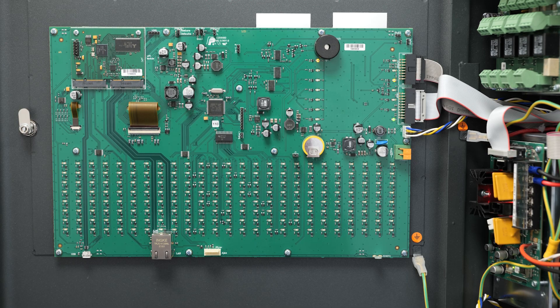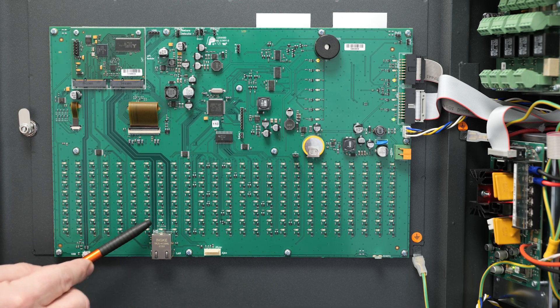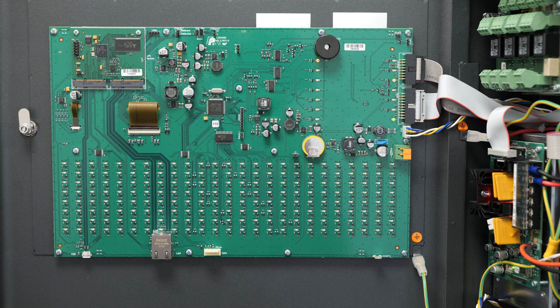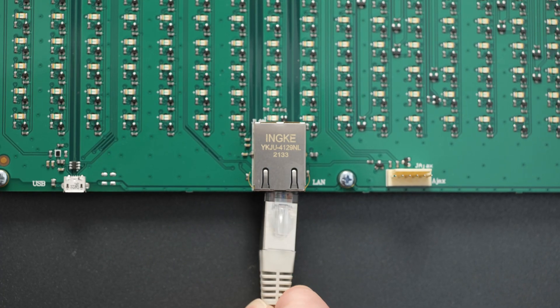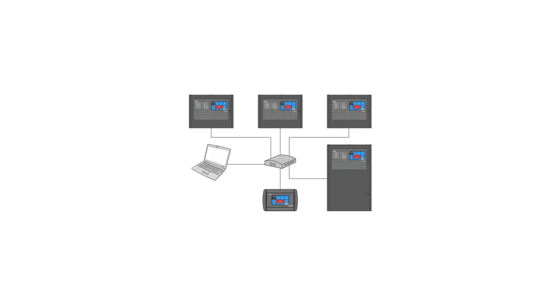As mentioned earlier, we can use the built-in LAN module of the Iris panels to create a network. We can use a standard CAT cable to connect the Iris panel to the LAN network. We have two options: to connect the panels over the internet, where every panel is online using a real IP and we are not limited in distance between the panels, or we can make a direct connection between panels, but in this case we need to use switches every 100 meters.